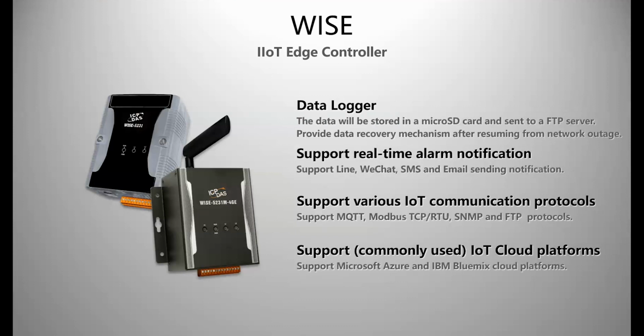Data logger. The built-in data logger of the WISE series provides the data recovery function. When a network failure occurs, the collected data will be stored in a micro SD card and resent to the control center after resuming from network outage. Support real-time alarm notification. The WISE series products support email, SMS, Line, and WeChat sending notifications. In the event of an error, the alarm notification will be sent to management personnel immediately.